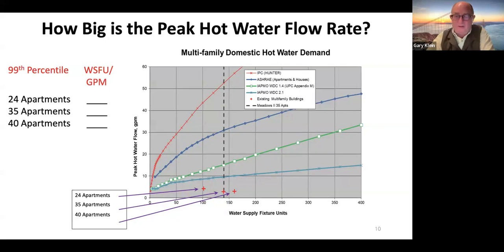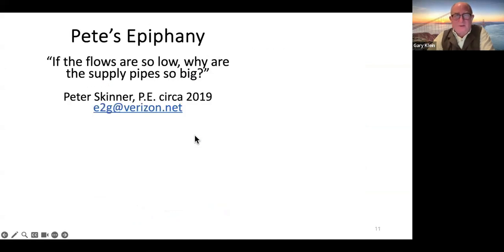For the whole building, we did the right sizing for the cold side too, but the hot side was already at 2.5 or 3 inches, which is nuts. So Pete's epiphany back then is, if the flows are so low, why are the pipes so big? And this was back in 2019. The water demand calculator had been issued in 2017, so this is early days.